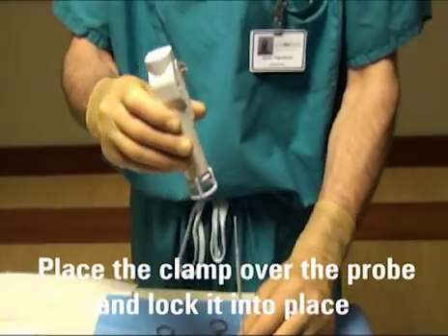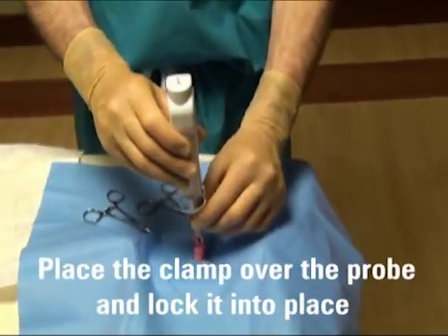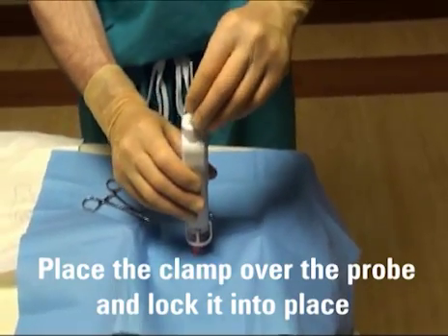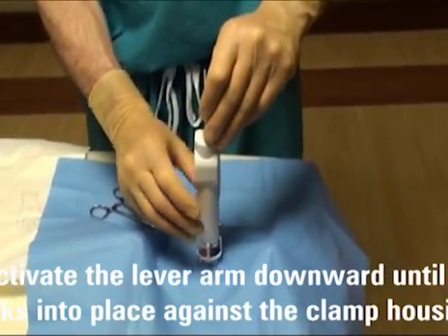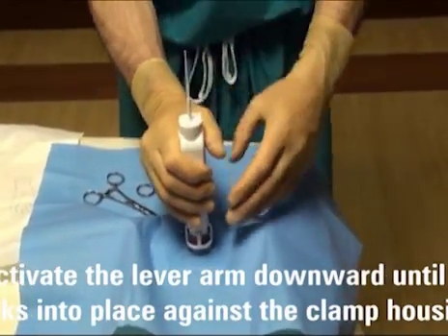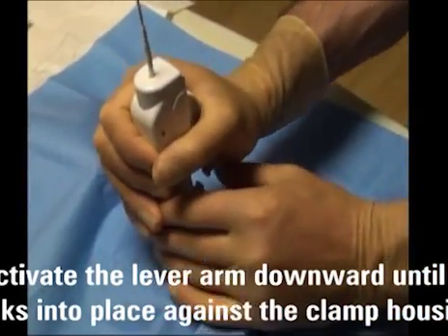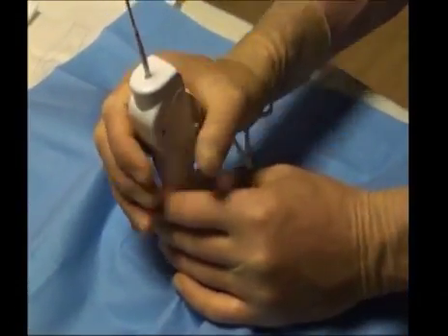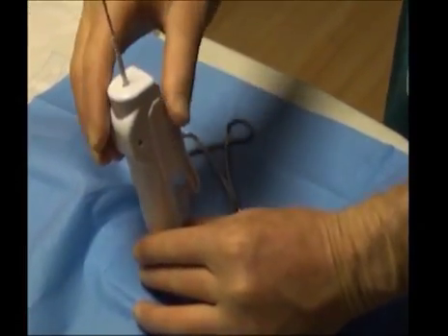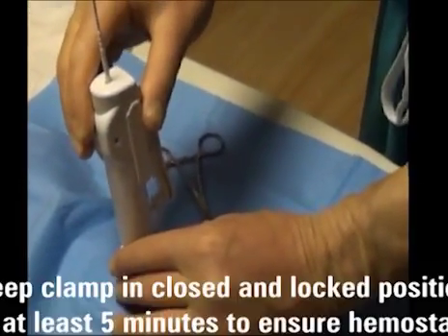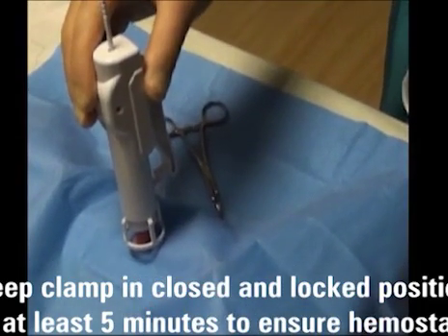Place the clamp over the probe. The probe will extend through the top of the clamp and will lock into place with an audible click. Then activate the lever arm downward until it locks into place against the clamp housing. As the lever arm is activated, the AccuCirc will crush and cut the foreskin, timed and executed by the device itself. Keep the clamp in the closed and locked position for at least 5 minutes to ensure hemostasis.